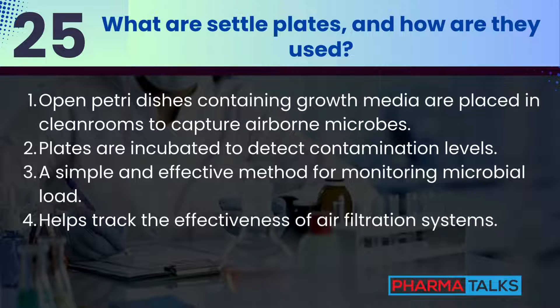What are settle plates and how are they used? Settle plates are petri dishes containing growth media left open in clean rooms to capture airborne microbes. They are incubated to detect contamination levels in the air. This method is simple and effective for monitoring microbial load. Regular use helps track the effectiveness of air filtration systems.